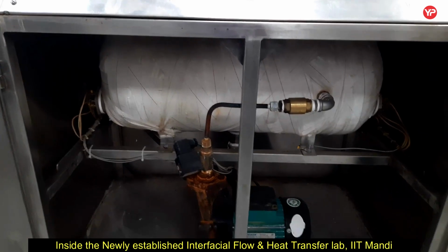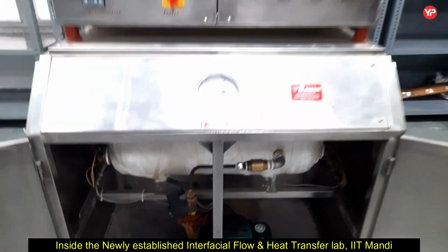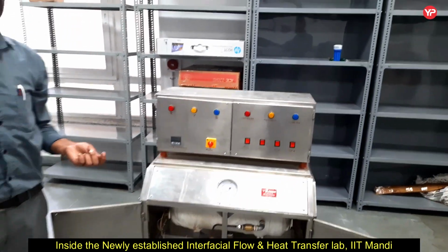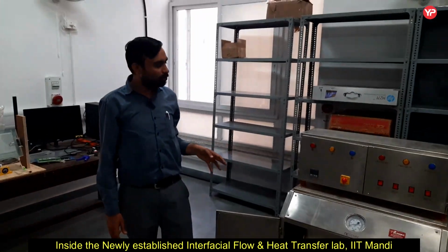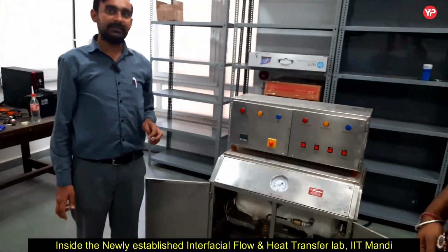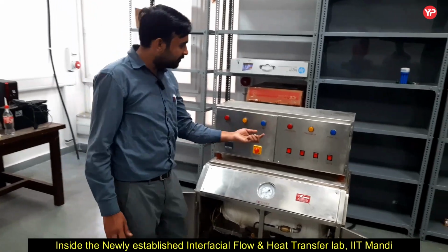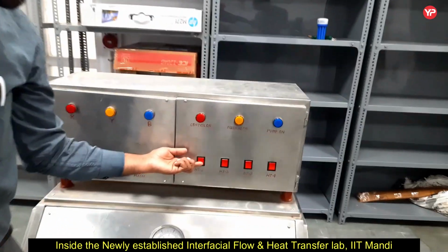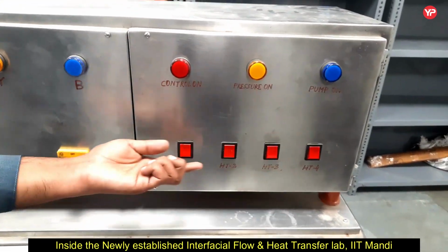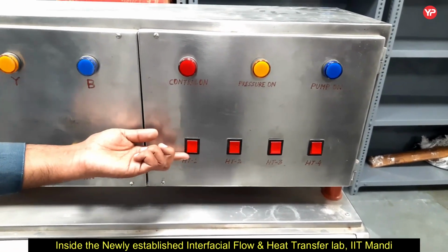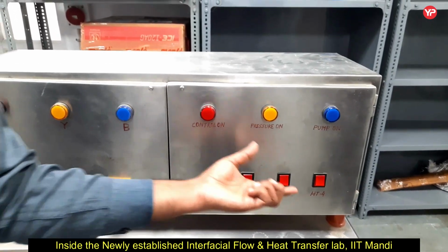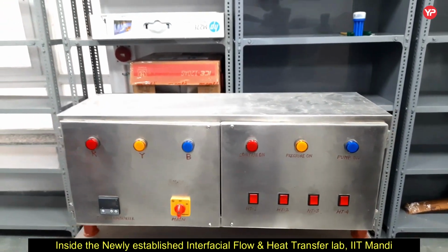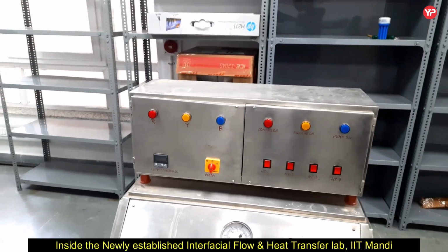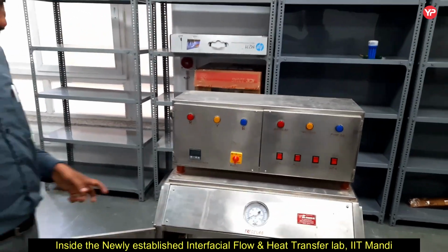Each of these four heaters has a capacity of 9 kilowatt, and altogether this boiler is of 36 kilowatts capacity. Over here we can see the switches to operate each heater. At a time I can switch on each heater individually, and I can also keep all four heaters, or any set of 2, 3 or 4, on simultaneously as per my requirement of the steam mass flow rate.